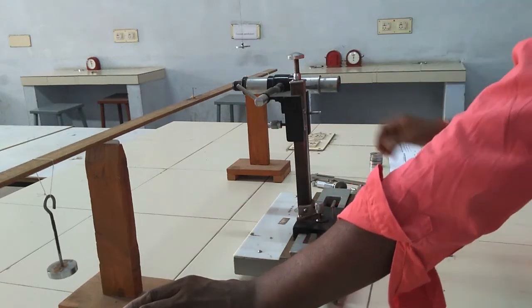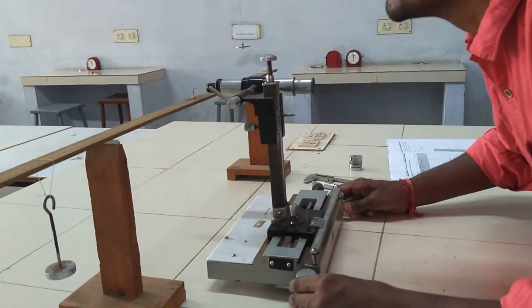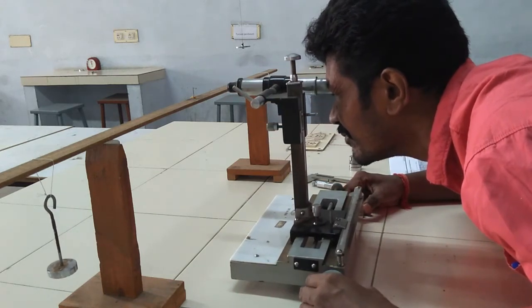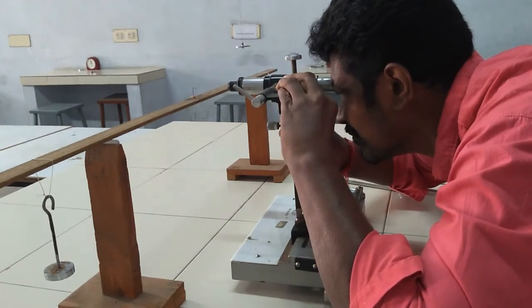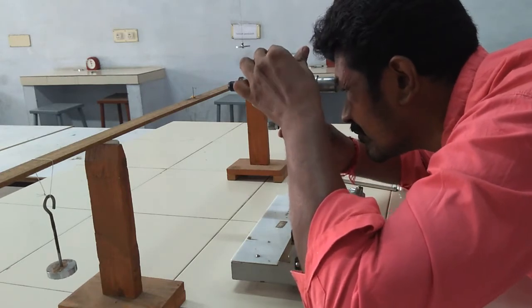The pin is set at the centre of the bar. The microscope views the pin image and optical images. Set the horizontal lines — this gives the reading. The pin image is set to the horizontal lines and readings are taken: Main Scale Reading and Vernier Scale Readings of the microscope.